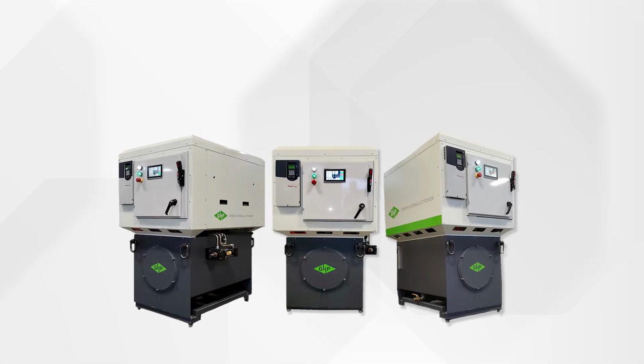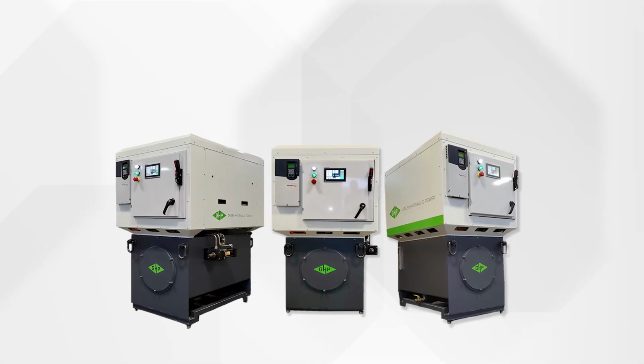Can you elaborate on how that helps reduce energy use? So what we do with these drives is basically reduce the motor speed. In a lot of manufacturing, there's a lot of dwell time where there's no action on the production line, so when there's no need for flow and pressure, we slow down the motor speed.